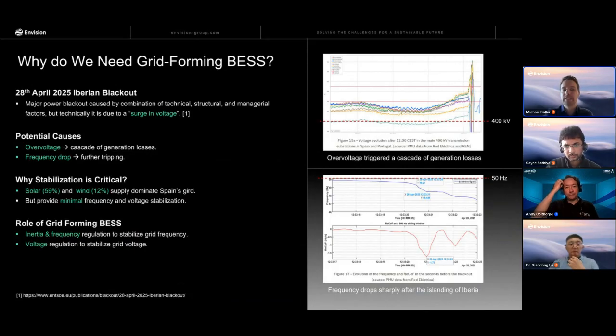But what grid forming does is provide stability and robustness, and with that, time. So instead of a couple of seconds, maybe you have half a minute or a minute of time to react, to bring the system back into a stable zone. And that time is really, really valuable to a system operator in Spain, but of course also to somebody like NESO in the UK. That's why they are willing to pay for this robustness and stability.